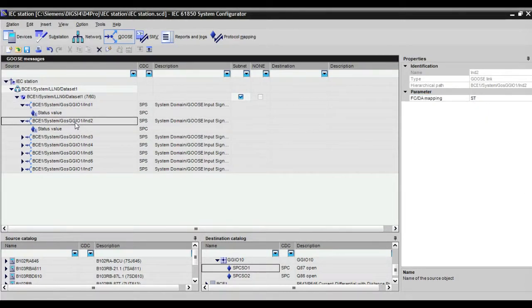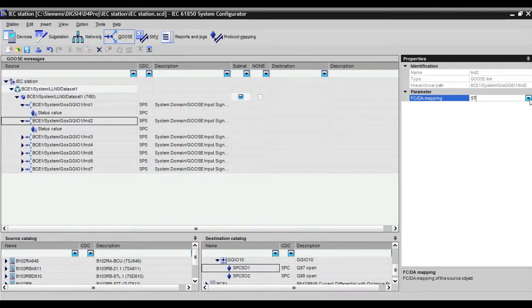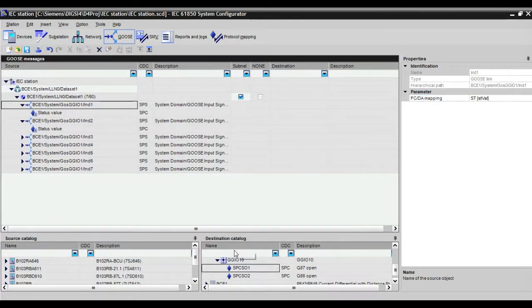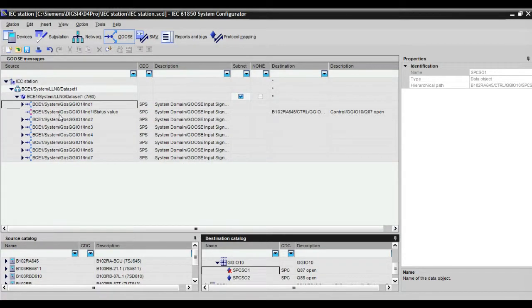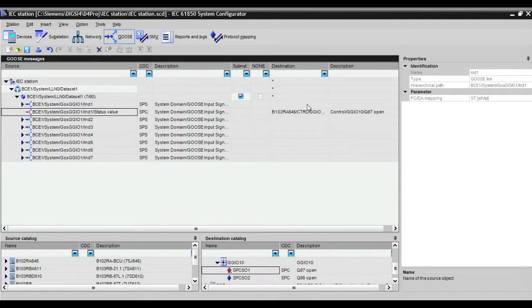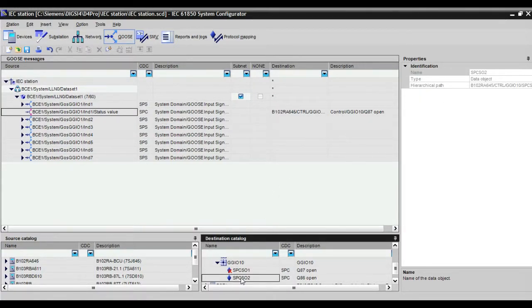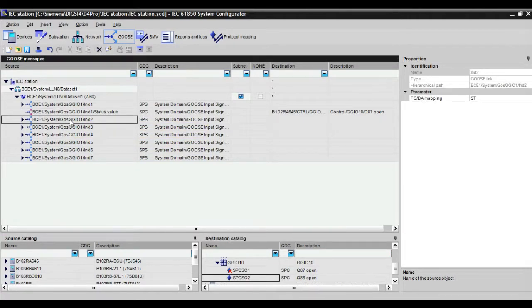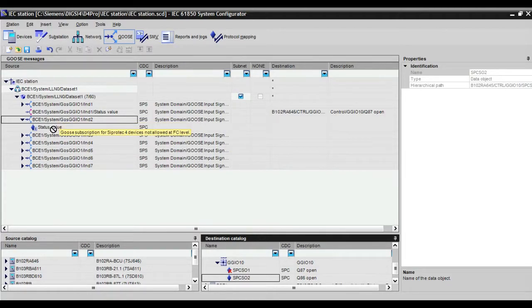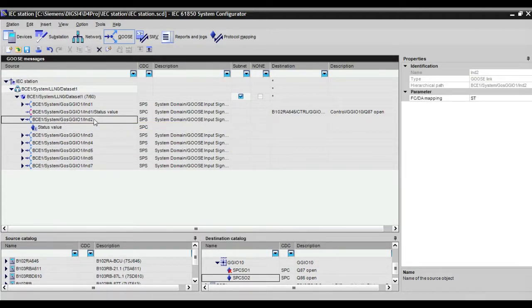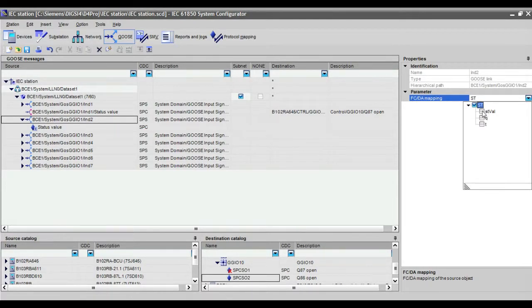And then you drag and drop from destination to your source. Our destination is Q87 open — this line isolator is assigned for virtual output 1. And Q86 the earth isolator is assigned for virtual output 2. After assigning, you save the file and go for updating the station. After updating you can write this file to the relay and you can see the GOOSE.